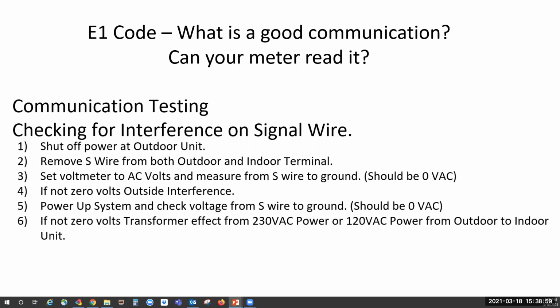All these readings can be done at the outdoor unit, where it's most of the time easier to work. Now you want to turn your power back on, with your meter set to AC volts again, and check the S wire to ground. You still should have 0 volts. If you don't have 0 volts, then you're getting what's called the transformer effect, which is what's affecting your wire.